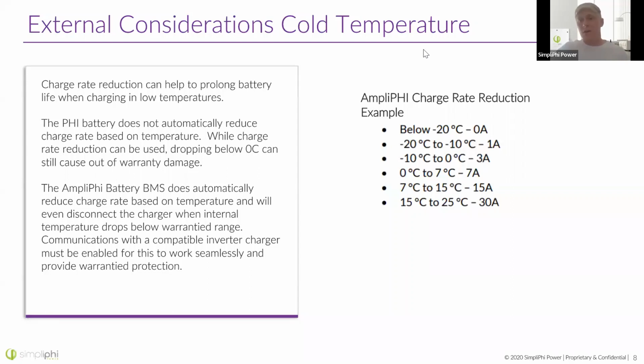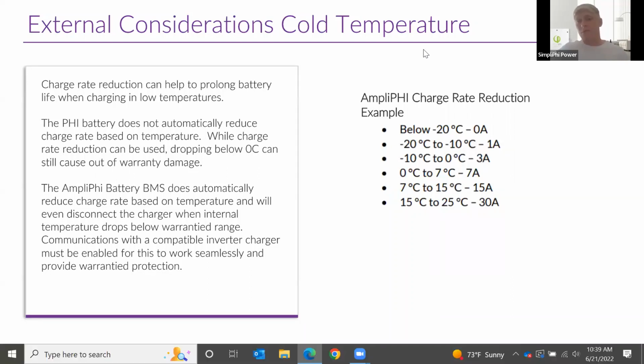The batteries themselves—I have never seen a battery capable of throttling current. But if this current is exceeded, it will just open circuit for the entire battery to prevent damage in a worst case scenario. Now, if you're a customer, you really don't want the battery opening circuit, because that means your power is out—your battery isn't backing up your loads. That's why you really should only use the SimpliPhi in applications where it is communicating. It will protect itself, but an open circuit means the system isn't operating perfectly.